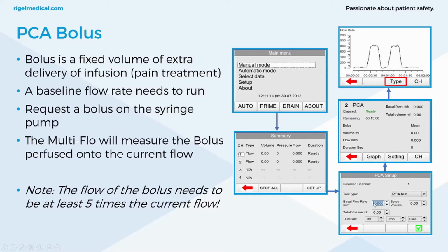So it's important to note when you're setting this up, the basal flow rate must be 5 times less than the bolus. So the flow of the bolus needs to be at least 5 times the current flow. So for this, the bolus volumes would typically be 100 mil per hour or more. And this gives you some more example of how this is set up. Once you actually go into the test, you've got these volumes on the screen, and you'll also have the numerical details.